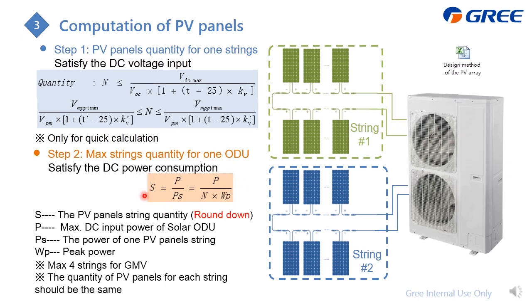For this you can find it: P is the max DC power of the solar outdoor unit, listed on the service manual. PS, N is the quantity of one string, which is the step 1 calculated value, and WP is the maximum output of the panel. Finally you can get the string quantity. The higher this value, the more strings you can connect, which also means you can save more power.